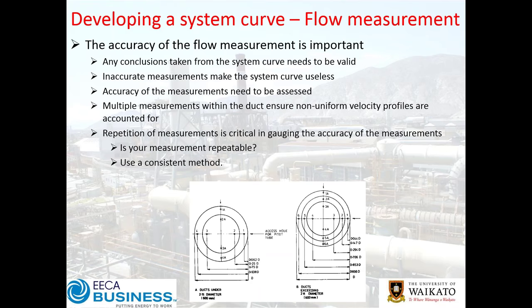Recommended sampling guides exist for different duct shapes — rectangular, square, and circular. Accuracy comes back to repetition, repeatability, and getting a representative measurement of flow across the duct. For smaller ducts you can get away with fewer points; for larger ducts you add multiple points for a better cross section. The main thing to remember is: is your method repeatable? If you go back and do the measurement again, do you get comparable results, or are they all over the place?